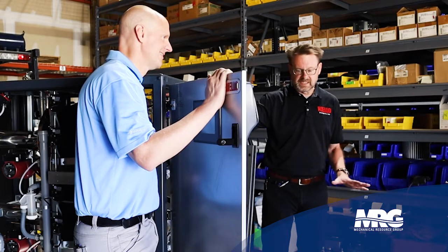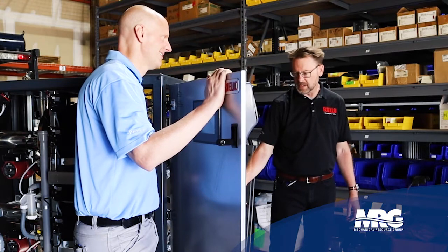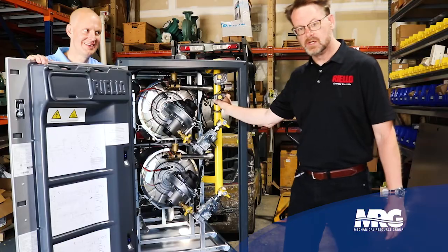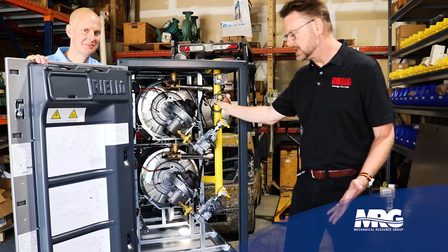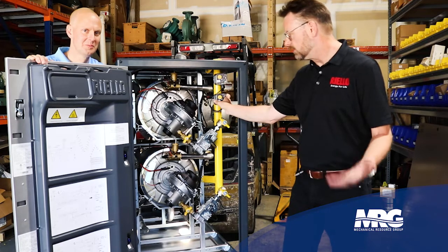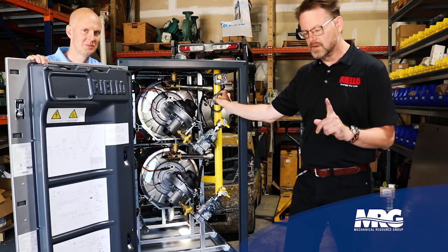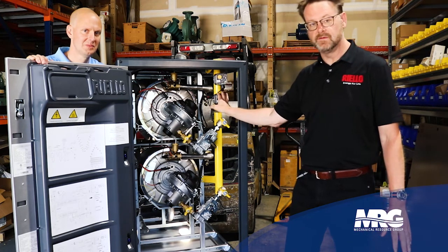Because there are only single points of failure on the cabinet, we can have those parts on hand to resolve them and restore operation. I was told last week by a technician that probably the second, third, fourth time they did something like this, it would take about 20 minutes. The first time, it might take them 30 minutes to swap out one of these single points of failure.